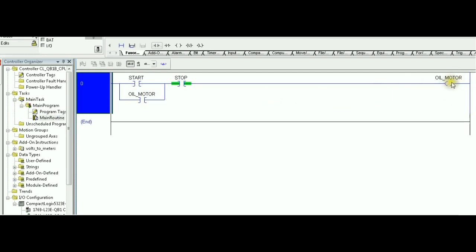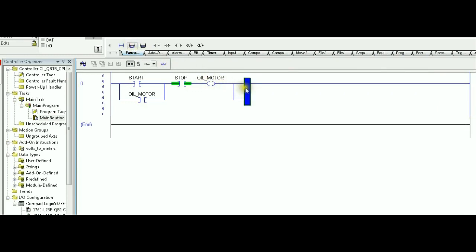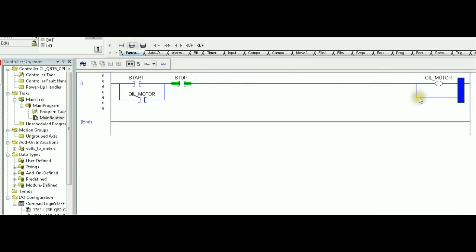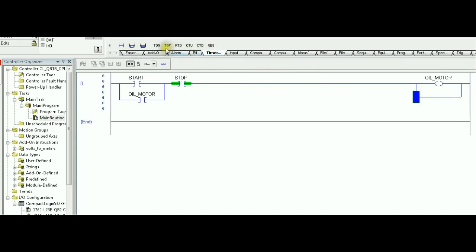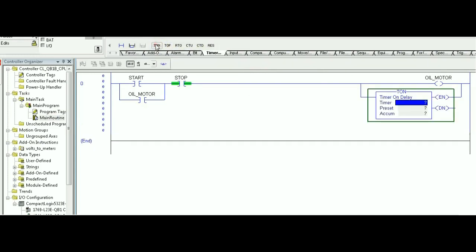Right now, the second requirement, or third requirement in that problem, it says 10 seconds after oil motor is on, we need the main motor to start. In other words, together with the oil motor, we need to start the timer. So, the timer, we insert from the timers tab. Insert TON because we agreed we are going to go with a non-retentive timer. The timer name is T1. The preset value in that requirement is 10 seconds, so 10,000 milliseconds. And the first rung is done right now.